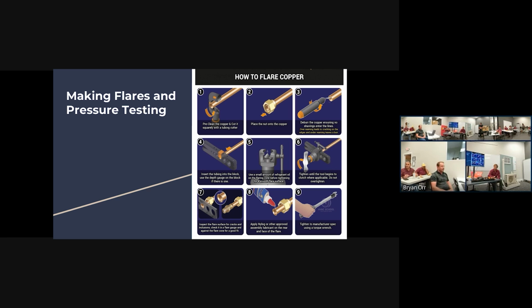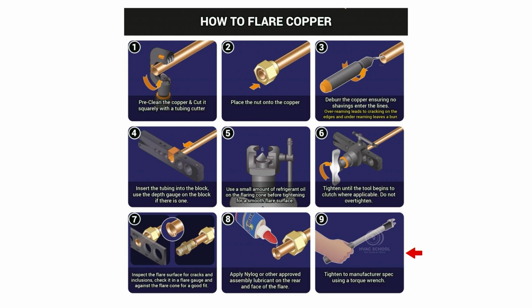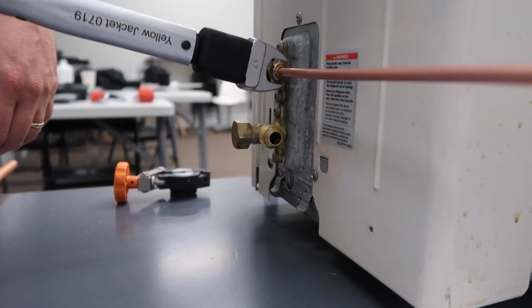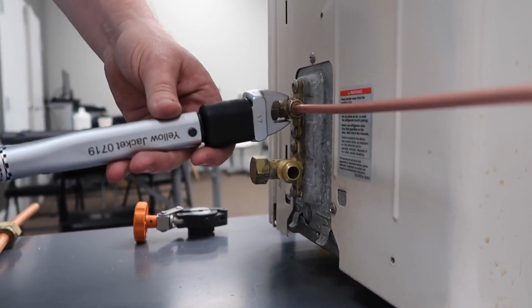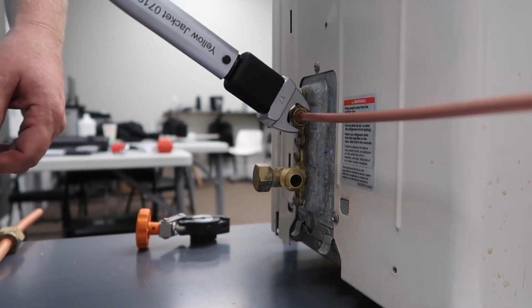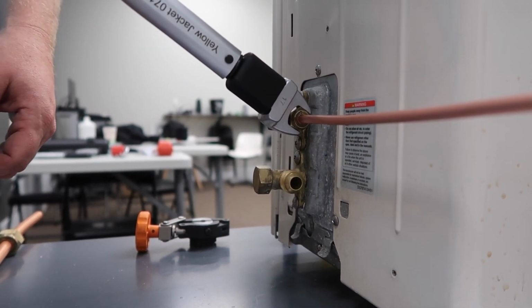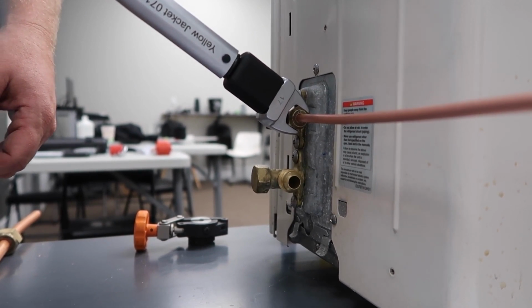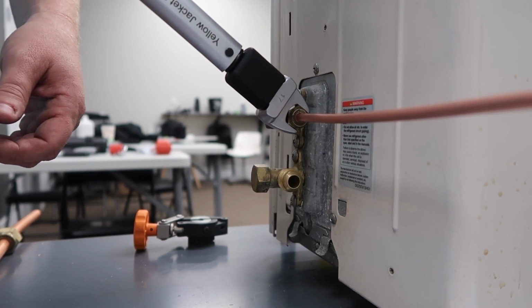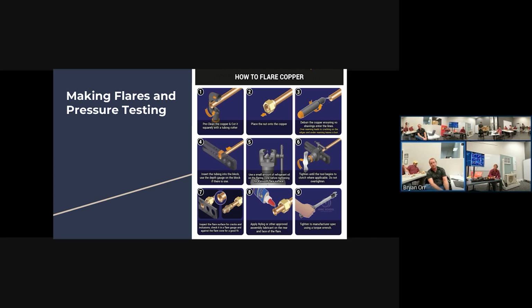So another thing to mention, the torque wrench that's shown in the photo here is not a digital torque wrench. It's manual, and it just gets to the right torque and does that clunk clunk motion. If you've ever used a traditional torque wrench, those also work perfectly fine. The one that's shown here is a Yellow Jacket that's designed specifically for flares. You can use a traditional torque wrench with a claw feature on it, with a crow's foot connection, but you just have to make sure that you're not extending the length, so you would actually have it at 90 degrees. Rather than having it straight out, that would extend the length and actually change the torque setting, whereas this Yellow Jacket one is actually designed for that.